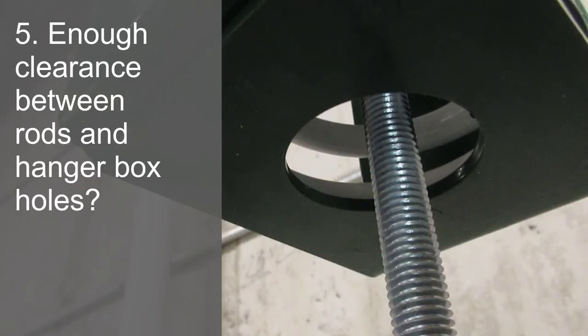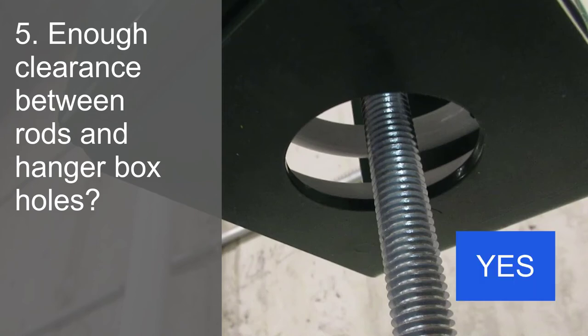Fifth, is there clearance between the rods and the housing holes? Yes. As we see here, the lower hanger rod is nowhere near the sides of the lower hole and has used only a degree or two of the 15 degree from vertical allowance.